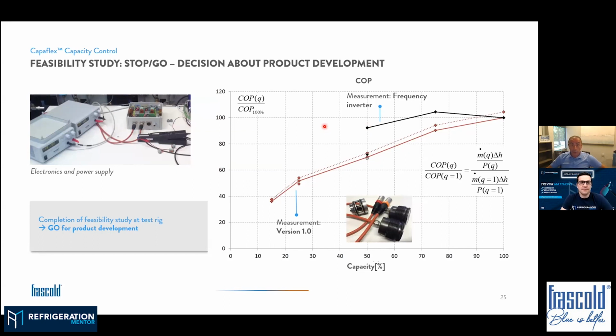And we saw what was the relative efficiency of this compressor. So even with a VFD, the curve is not flat, you are still losing almost 15% of efficiency, because you go as low as 85%. So we measured on our very first prototype that we were capable of reaching 70% of the efficiency. So we said, this is a good starting point.